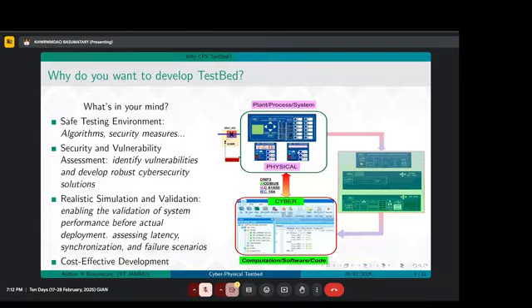So what happens is that suppose this relay has some data, and I take this data to the RTAC, and the RTAC is conditionally sending signals back to the relay, and the relay changes the breaker, whether it should be on or off. So this decision is made by the algorithms written in the RTAC. These signals get exchanged between the cyber and physical parts. It's possible because of DNP, Modbus, and IEC 61850 or some other protocols.